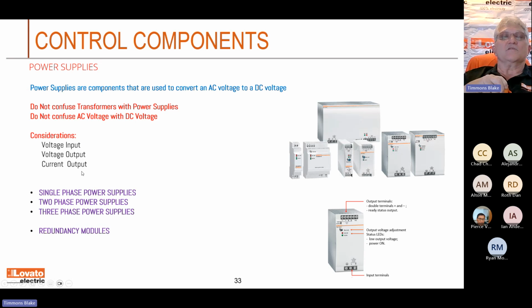without any ripple. So even if you had the old linear style power supplies, you had a little bit of ripple in there. It wasn't a true 24 volts DC. You could actually see some ripple in there. But now their ripple was like 0.1 volt peak to peak. But now with these new switching power supplies, you're like 0.01 peak to peak. So you got a lot cleaner power supply. And also a lot of power supplies, since they have such capacitors in them, as you power it down, it still holds the power. Ride-through, I think they call it.